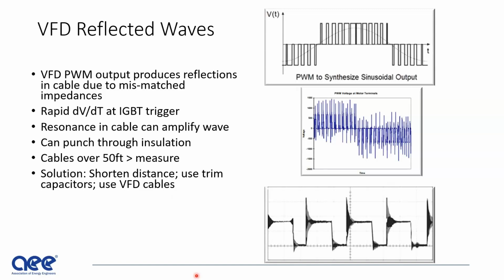The reflected waves: we talked about these rapid dV/dt voltages that come off of a VFD motor interaction. You need to be less than 50 feet on that cable. When you get over 50 feet on the cable between the VFD and the motor, you're a prime candidate for resonance in that cable, and reflected waves could very much affect the performance of your installation.